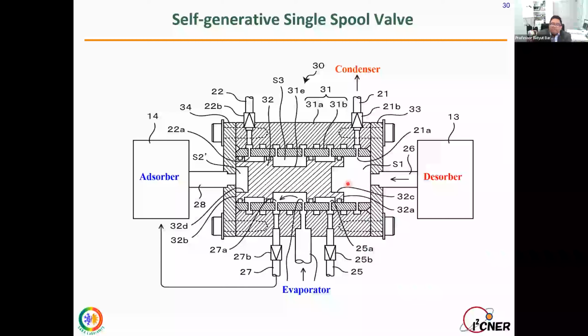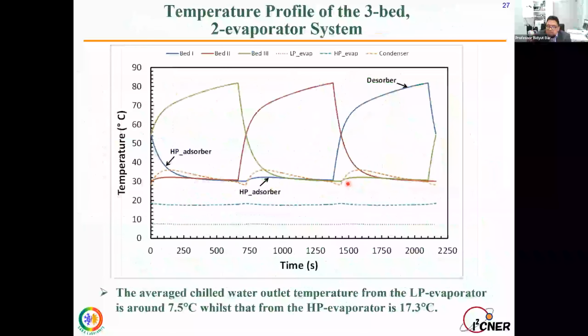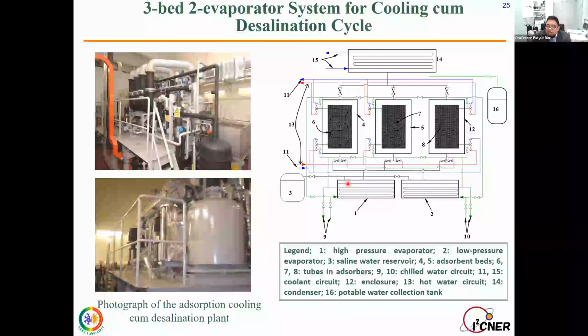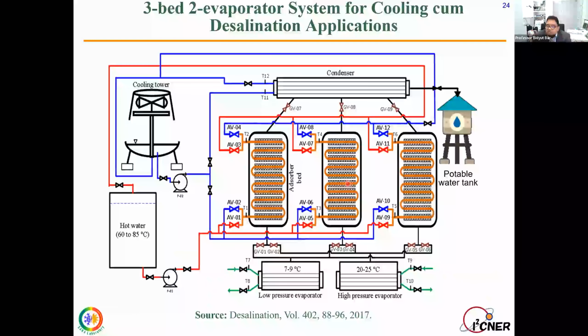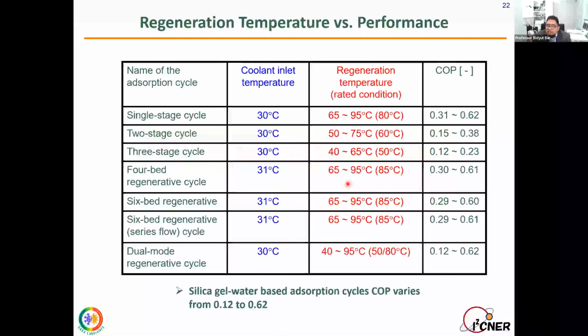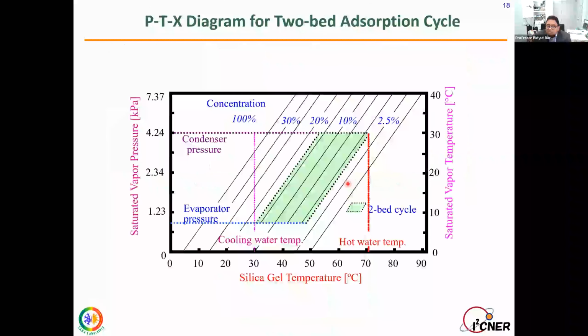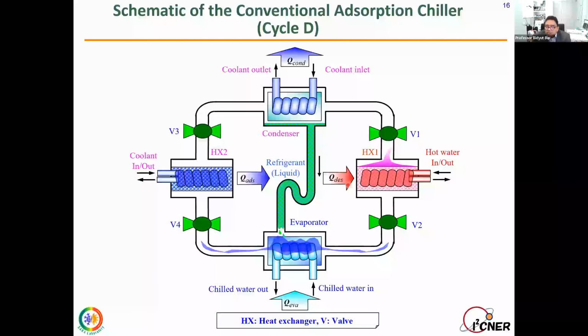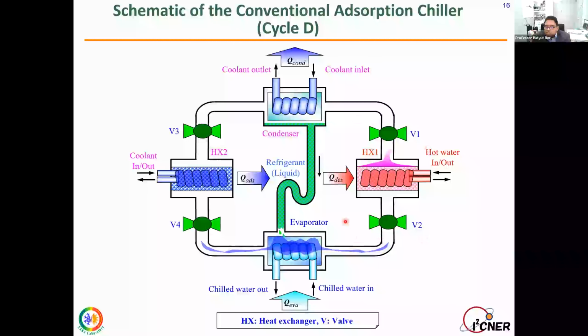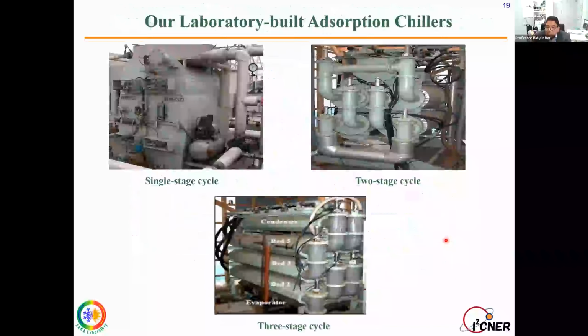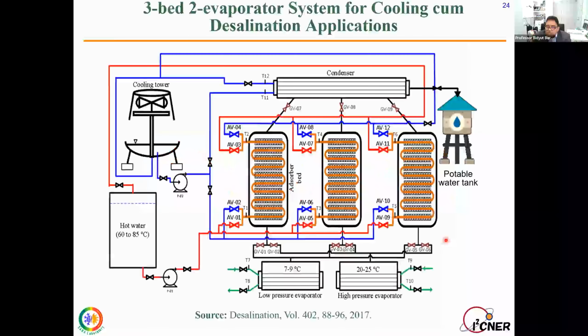So this is a kind of single spool valve. Here in our systems, I will just go quickly. As you can see in the basic system, for example, we need at least 4 refrigerant valves here: 1, 2, 3, and 4. These are electromagnetic valves. They are expensive, and they also take up some space, but we can eliminate all these valves with our new innovations.